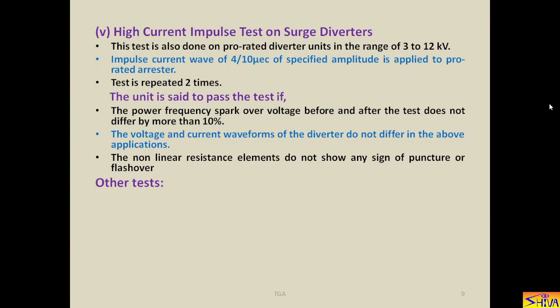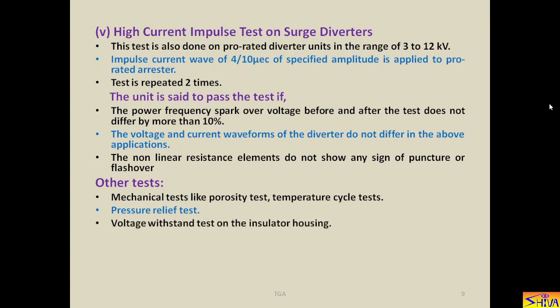Other tests which are performed on the lightning arrestor are mechanical tests like porosity test, temperature cycle test, pressure relief test, voltage withstand test on the insulator housing, and switching surge flashover test, as well as pollution test. So these are the other different tests to be performed on lightning arresters. Friends, now I have completed the high voltage testing of major electrical equipments. In this video lecture, I have explained the high voltage testing of lightning arrestor.